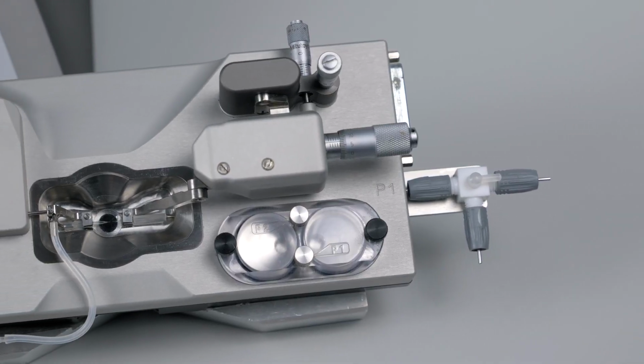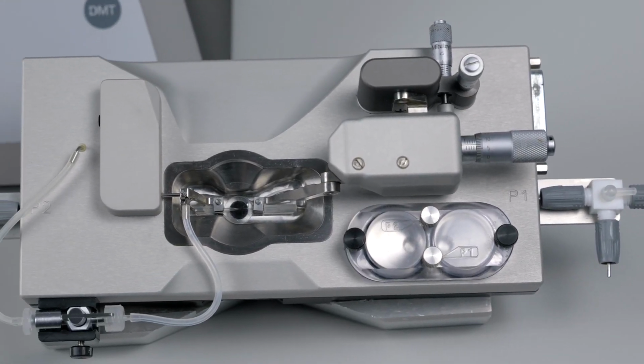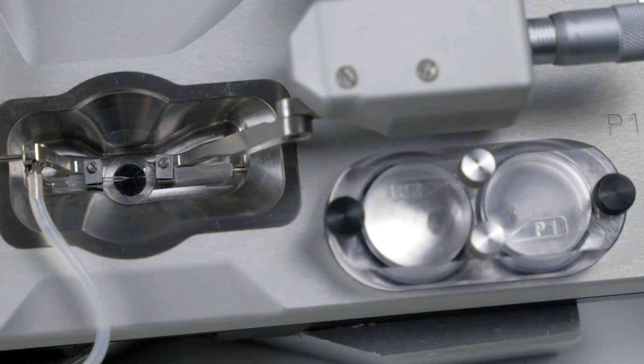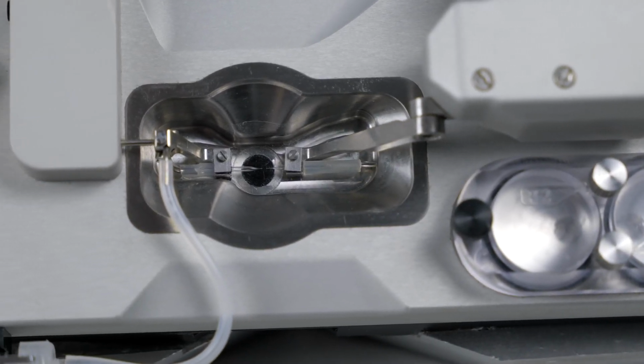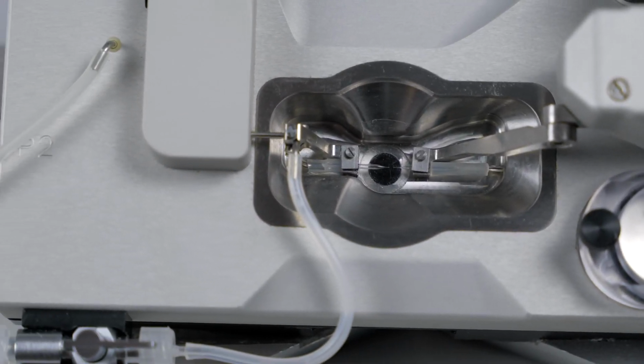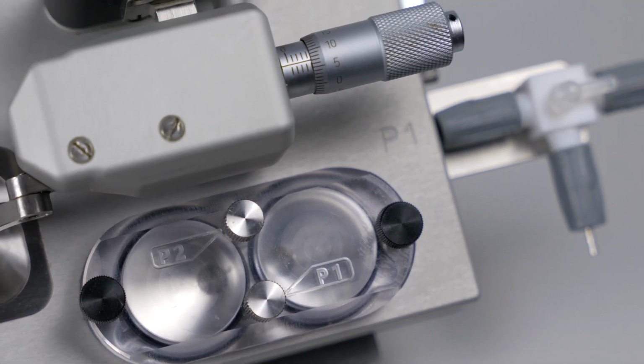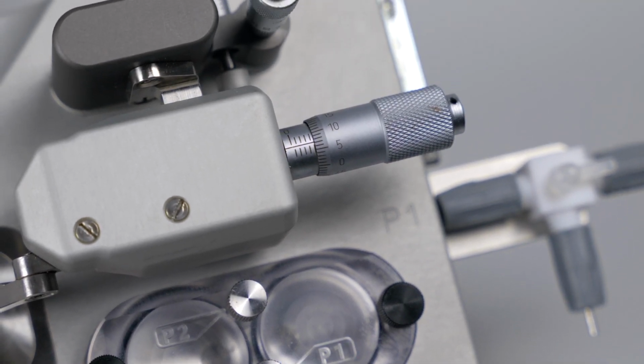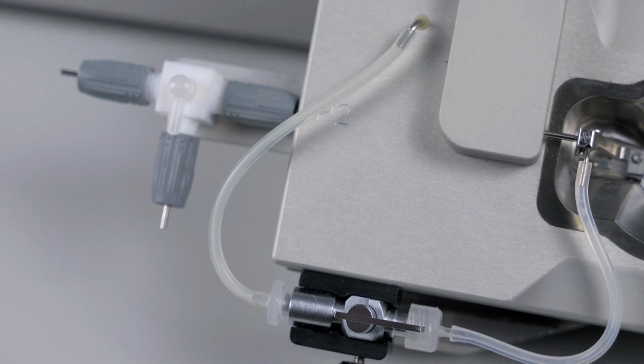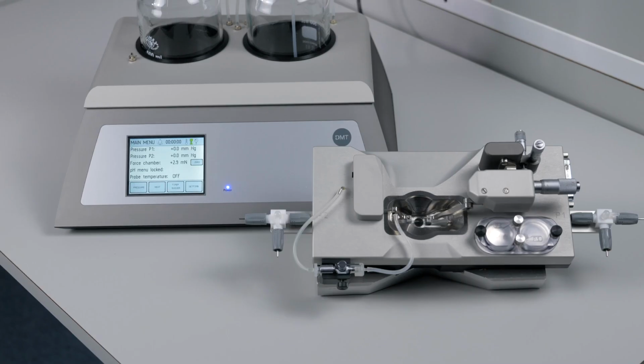The 112 PP is unique in the commercially available pressure myograph field. The system allows users to study isolated vessels under pulsatile pressures which mimic the effects of the heartbeat on your tissue. You can set a high and a low pressure, including 50 to 600 beats per minute. The user can perform flow-mediated experiments or blind sac steady pressure studies.